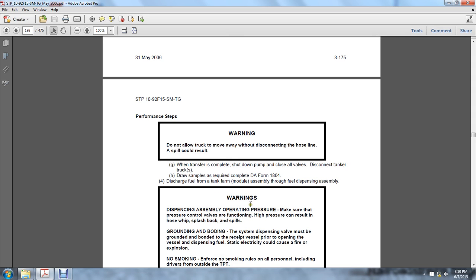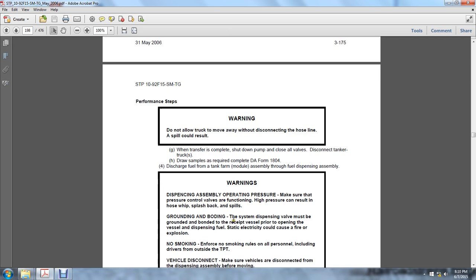Warning, dispensing assembly operation pressure. Make sure that the pressure control valves are functioning. A high pressure can result in a high hose whip and splashback spills. Grounding and bonding: the system dispensing valve must be grounded and bonded to the receiving vessel before opening the vessel. Dispensing fuel without this, static electricity could cause a fire or explosion.